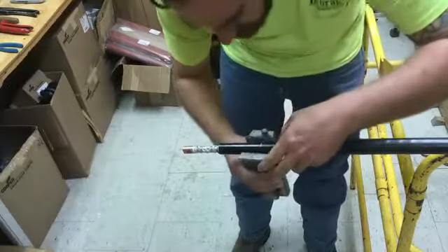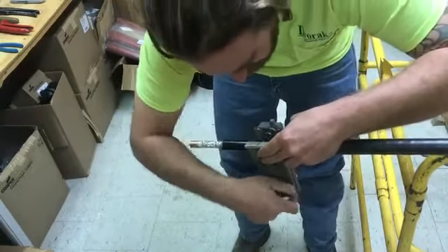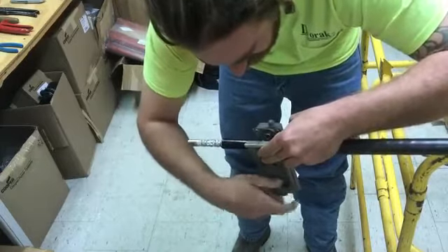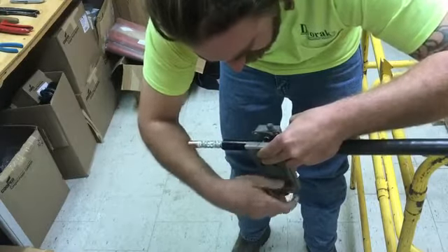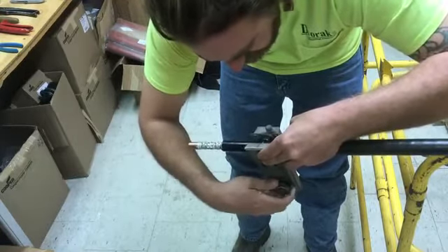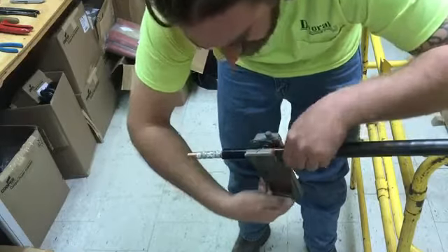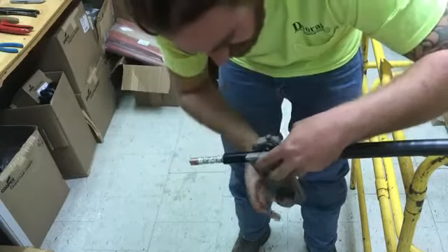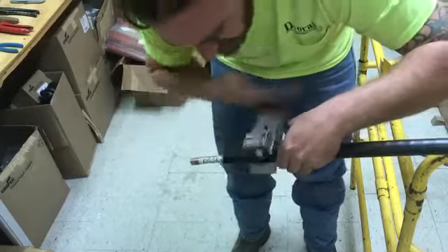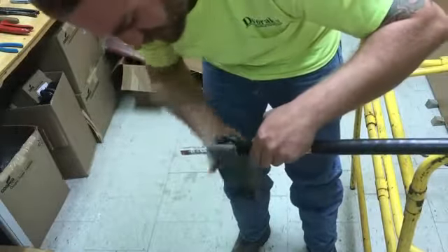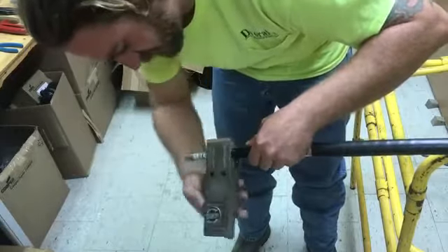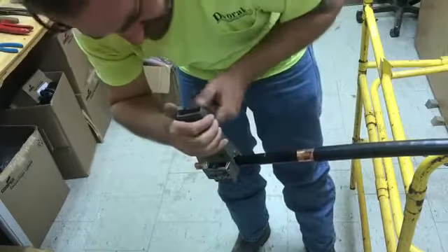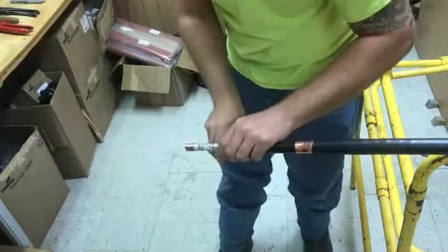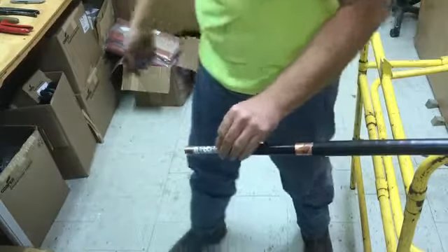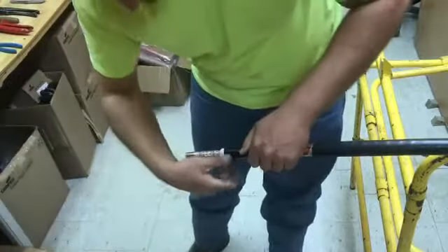Using the semicon scoring tool, I'll make the initial square cut, then switch the tool over to spiral cut and spiral to the end of the cable, removing the tool. It's good practice to do a test cut with your semicon score on a scrap piece of cable or the very end of the cable to ensure that the blade depth is not too deep and will cut into the insulation below. Using the duckbill pliers, I begin peeling back the semicon layer.